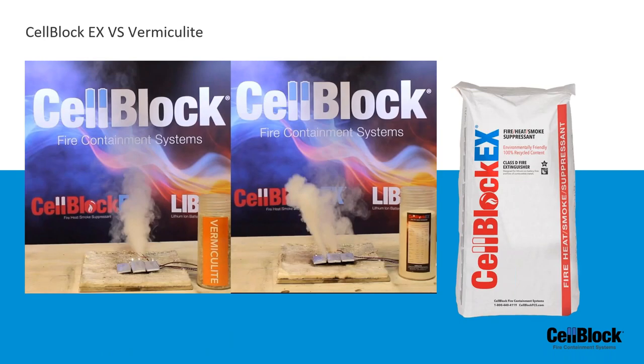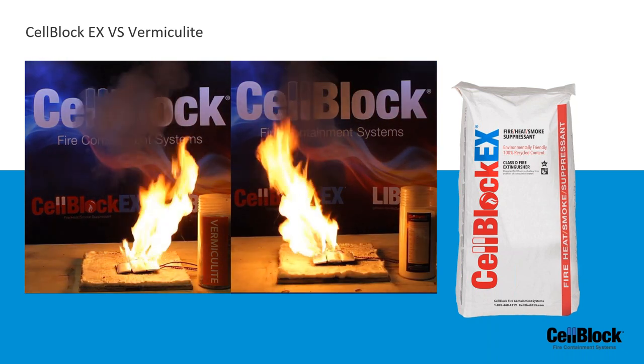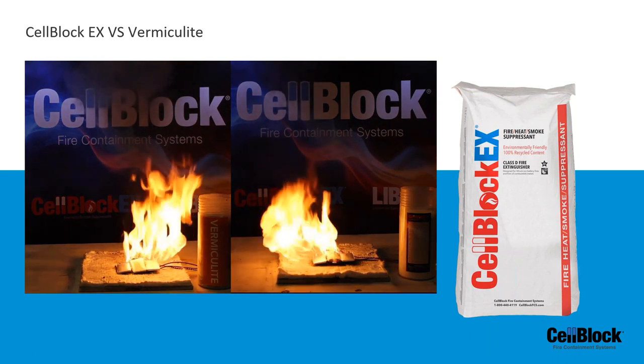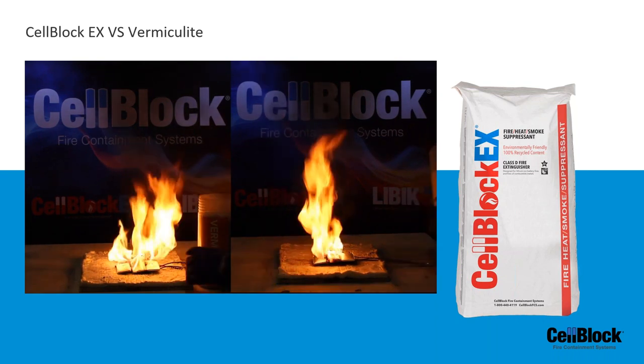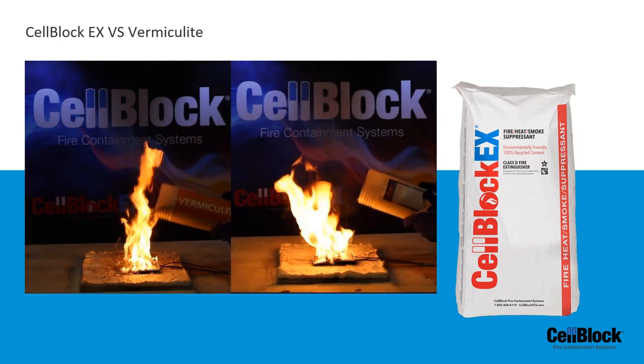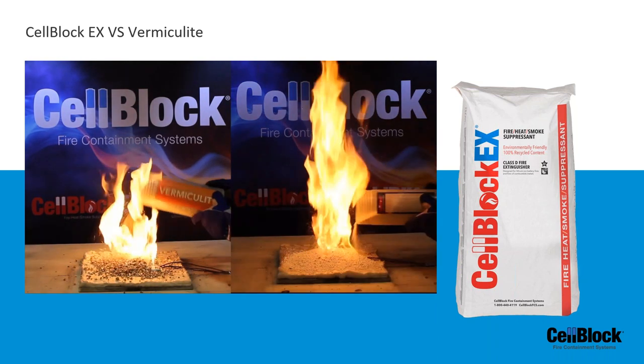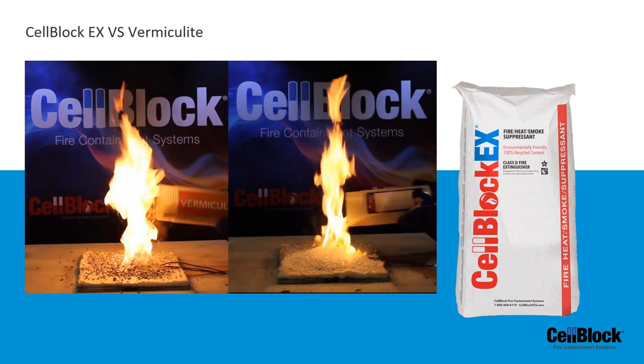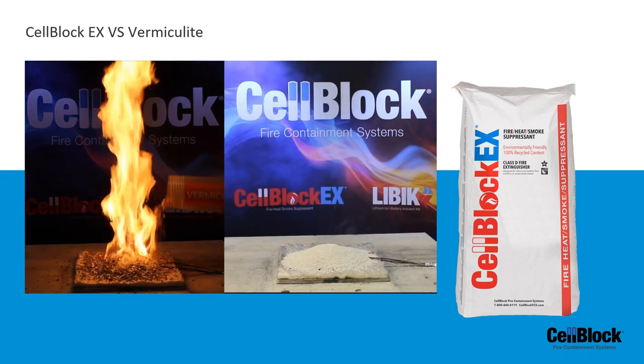Perfect. So CellBlock EX versus vermiculite. This is a really great video, and we just like to show the performance here. What we have is polymer packs, three polymer packs on each side. On the left side, we're going to try to extinguish it with vermiculite, and on the right, you're going to see the CellBlock EX deployed. What you'll see here is the speed at which the CellBlock EX completely extinguishes the fire. You can see the material flowing into place much better, and it's completely out.